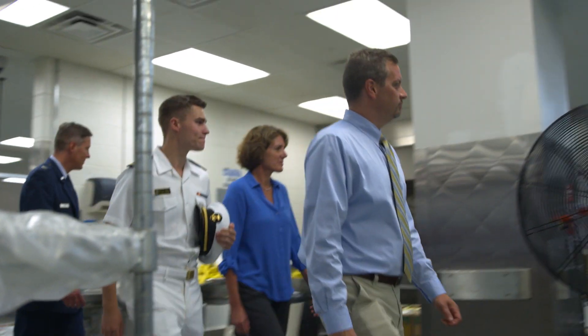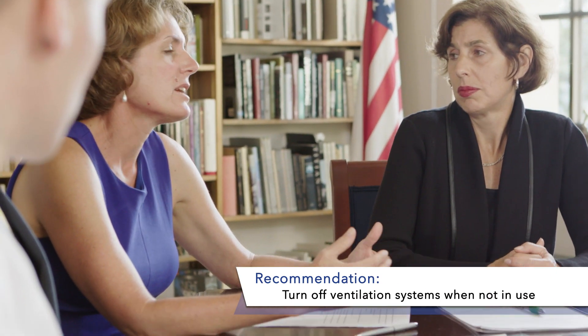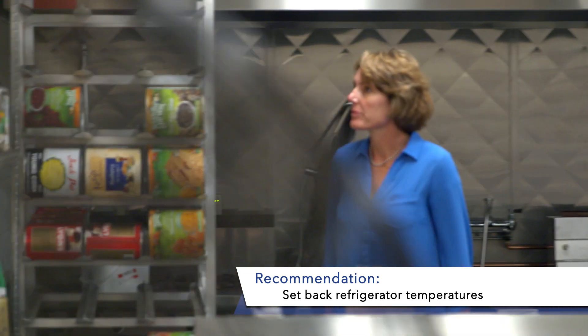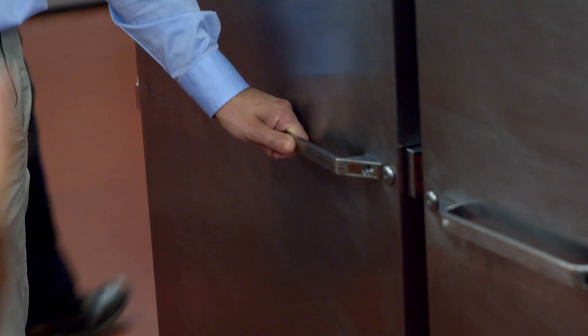Sounds like the vents are on, and there's really not much going on in here right now. An interesting thing I found in the kitchens — some ventilation systems were on when they didn't need to be, some refrigeration systems seemed excessively cold, there was even frost built up on the outside of them, and we found some doors that didn't close properly. I think just looking at those types of things and training is an opportunity for you all.